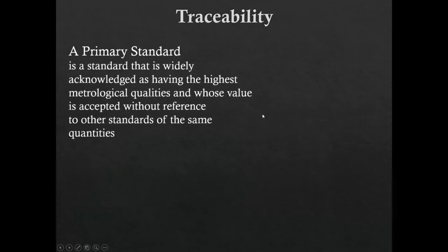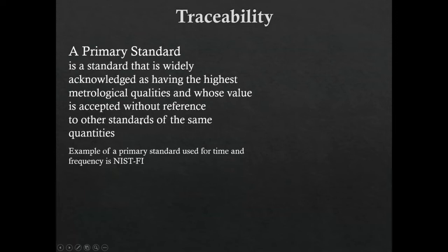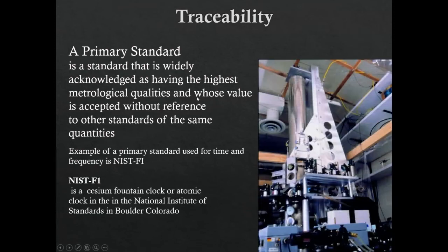A primary standard is one widely acknowledged as having the highest metrological qualities, whose value is accepted without reference to other standards of the same quantity. Whether it's temperature, pressure, mass, or time, the primary standard is the top of the pyramid. An example for time and frequency is the NIST-F1 standard — a cesium atomic clock residing in Colorado. Time isn't something we generally calibrate for directly, but many things we measure are relative to time, so it has a standard as do most other measurements.